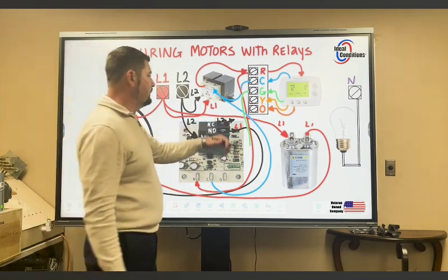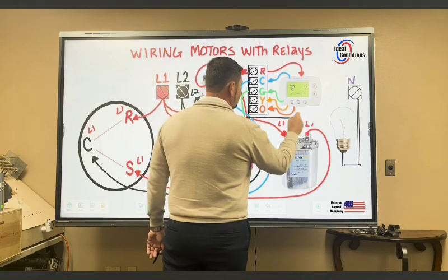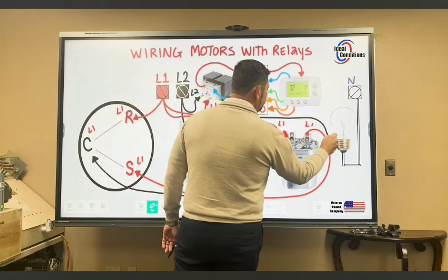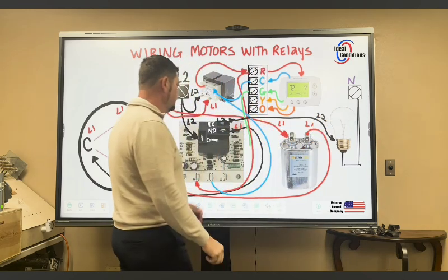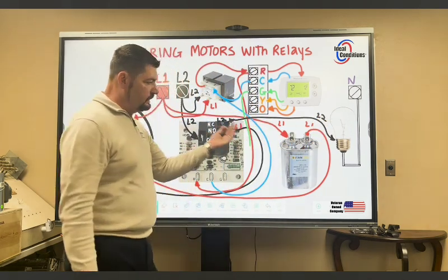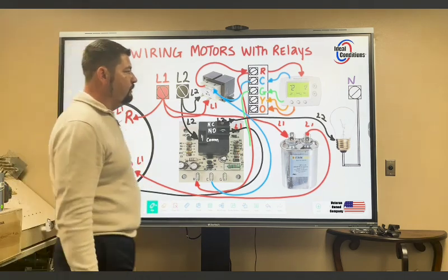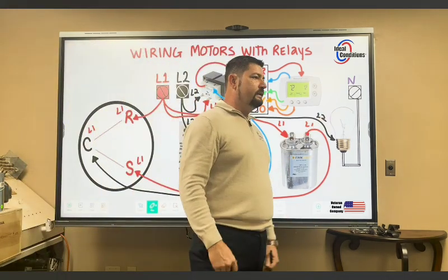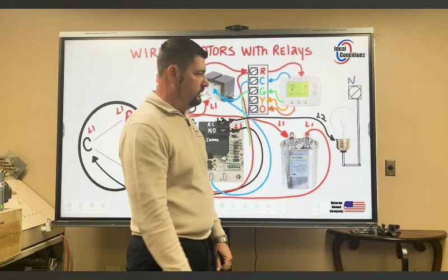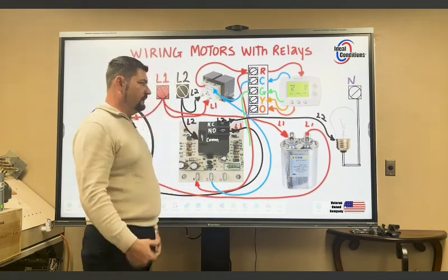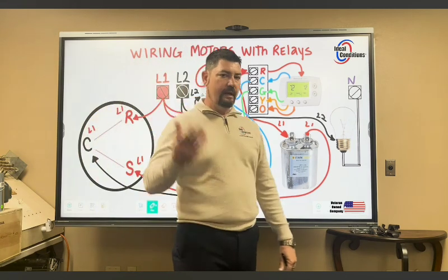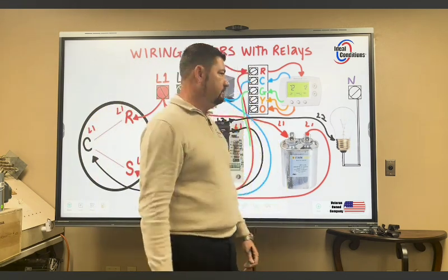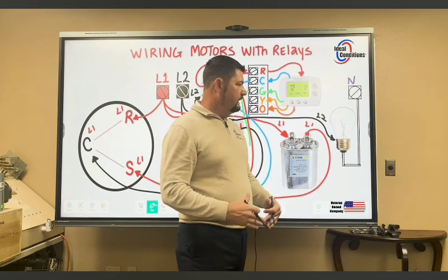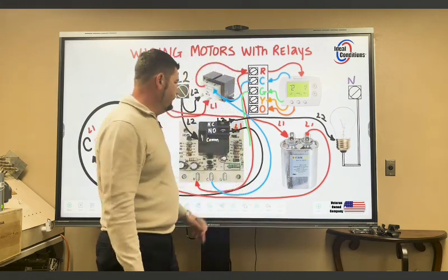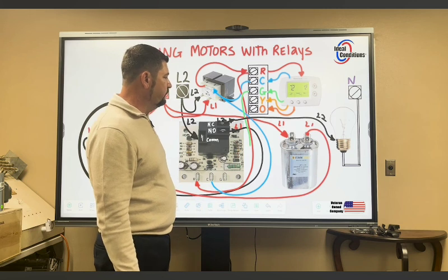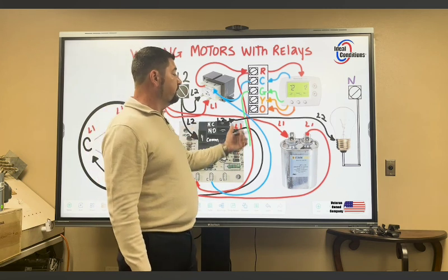So if I wanted to wire up my light bulb, I would actually come off of this, and I would come over to my light bulb, and I would say, when I'm not running, if I wired that over to here, then my light will be on. And say I wanted to say that when that light is on, that's an indicator that the machine is off. And when the light is off, that's an indicator that the machine is on. And how do I know the machine is on? I feel air coming out of the vent. If I don't feel air coming out of the vent, I got a light bulb. It's whatever you want to do. That's more building automated stuff, where we need these normally closed terminals to do something for us. I just want to show you that you could do something like that.